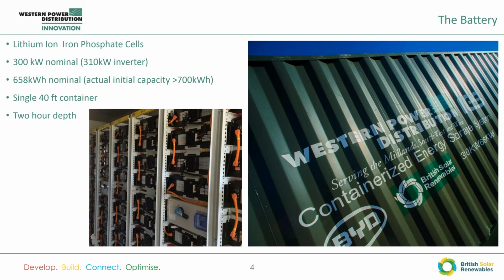The 2-hour depth was to help cover off all of the use cases, although it has been noted that the standard commercial depth of a battery throughout this project will be 1 hour. And we initially ran this battery between 20 and 80% state of charge limits, which we then extended to 90 to 10% as we grew more confident with the battery. Contractually, we were allowed to charge and discharge between 1 and 99%, but we put extra limits within Resolve to ensure longevity of the battery.